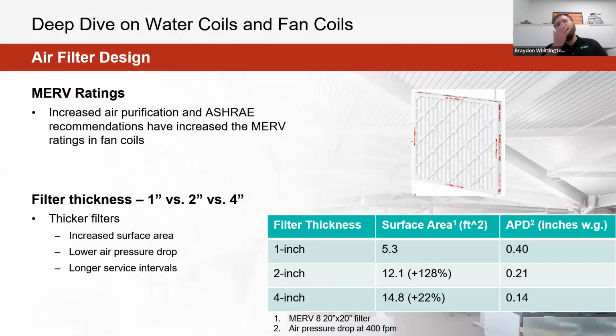And the last component, because all of these products are also being provided with filters, is consideration of what filters are being added to these products. With fan and blower coils, what we're seeing is a shift to thicker and thicker filters that are going to be paired with these products. Benefit from that is not only from a filtration perspective, but by increasing the overall surface area of that filter, what that actually does for us is decrease the amount of resistance or air pressure drop that filter is adding to that fan coil, or that blower coil here. So for example, we're seeing a step to a 2-inch or 4-inch filter, almost halving the amount of air pressure drop that's happening at that filter, as it's going to be having air passing through it for its first resistance.